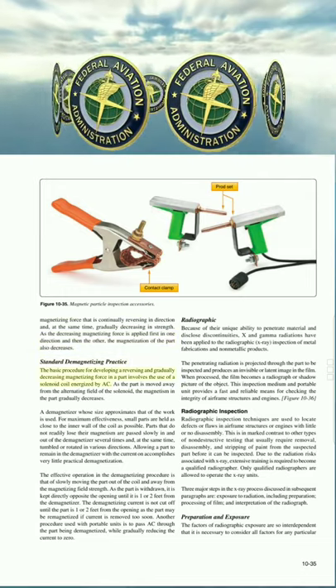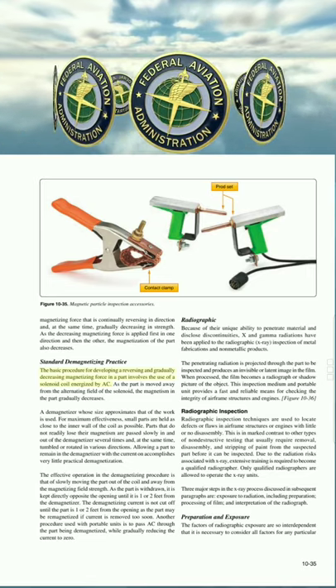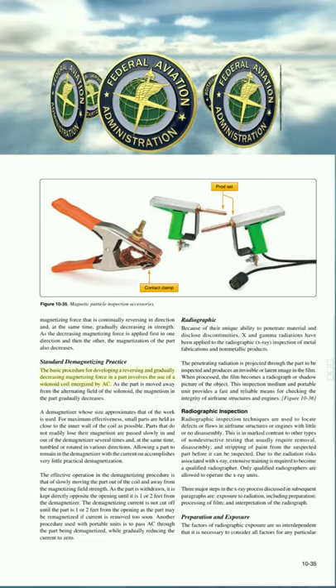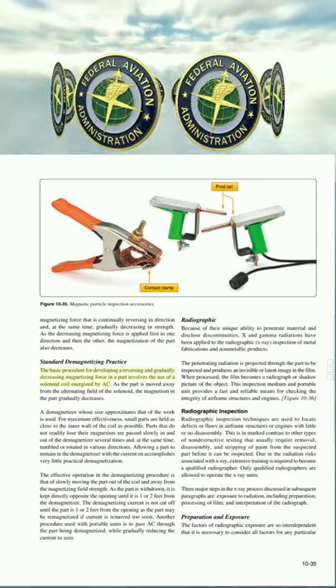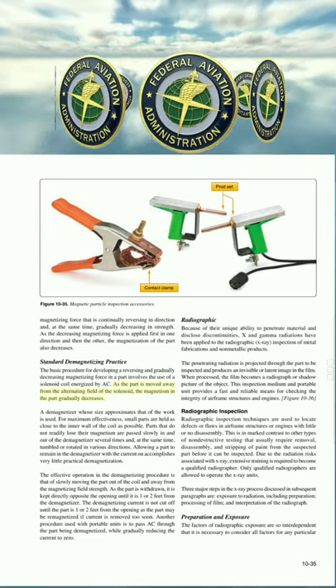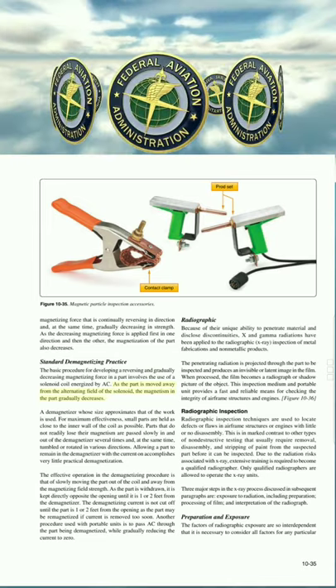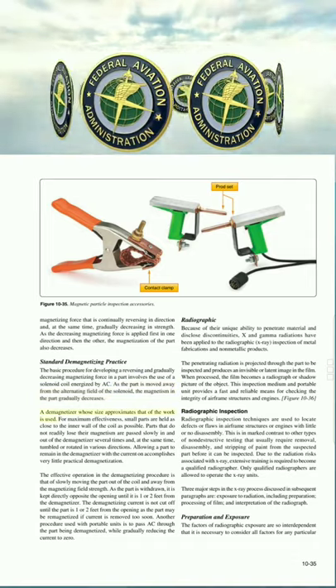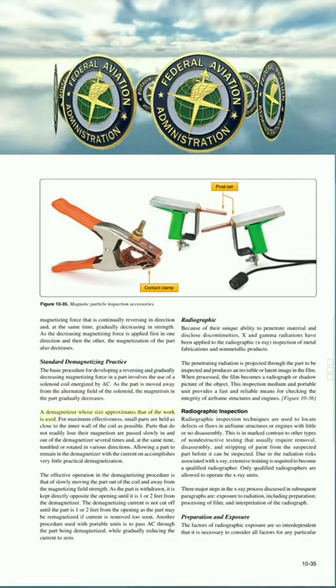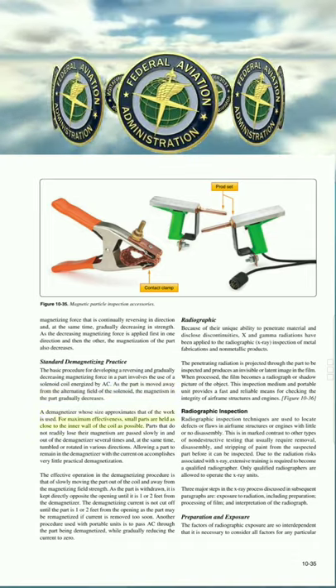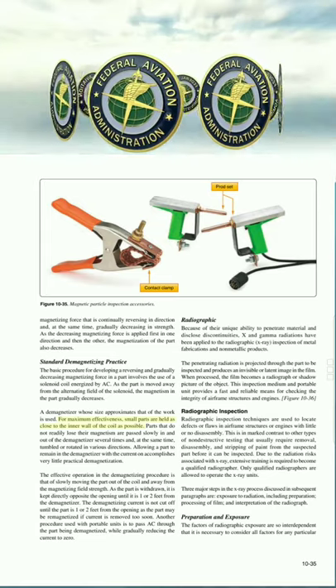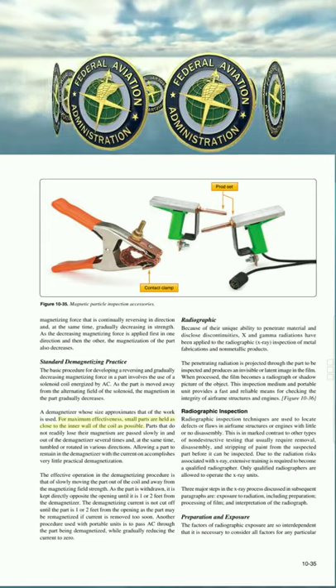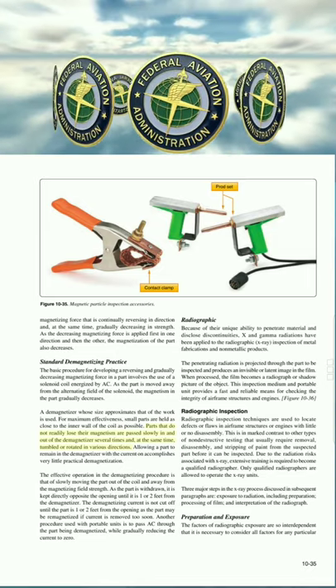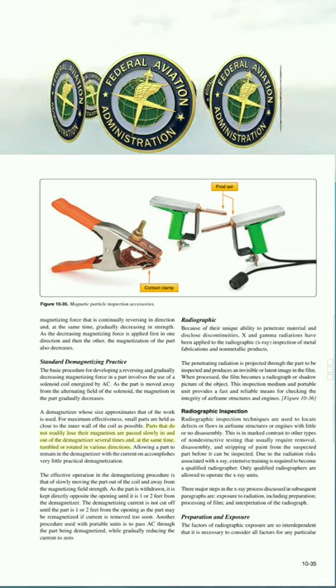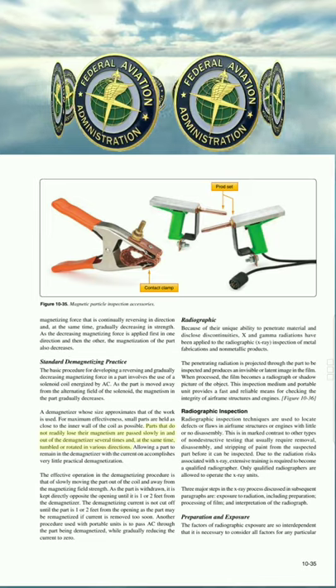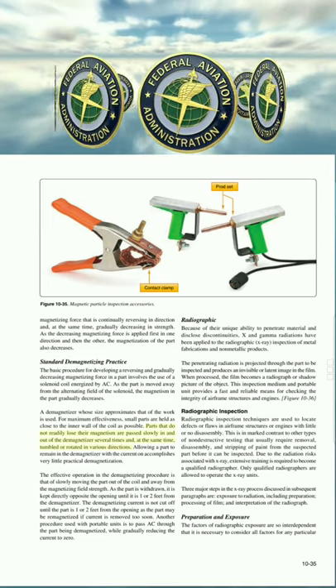The basic procedure for developing a reversing and gradually decreasing magnetizing force in a part involves the use of a solenoid coil energized by AC. As the part is moved away from the alternating field of the solenoid, the magnetism in the part gradually decreases. A demagnetizer, whose size approximates that of the work, is used. For maximum effectiveness, small parts are held as close to the inner wall of the coil as possible. Parts that do not readily lose their magnetism are passed slowly in and out of the demagnetizer several times and, at the same time, tumbled or rotated in various directions.